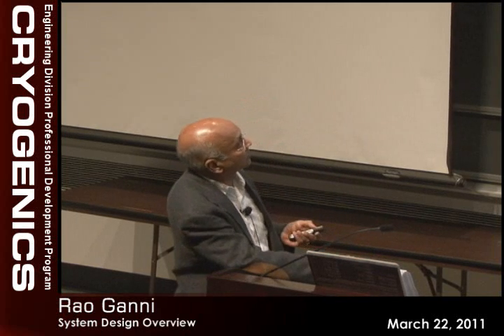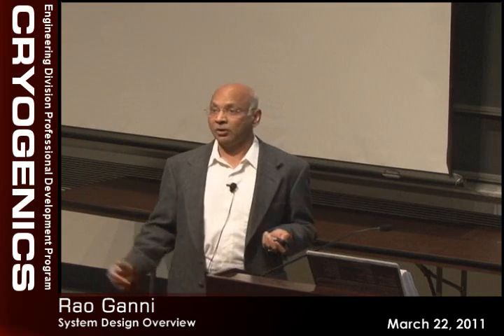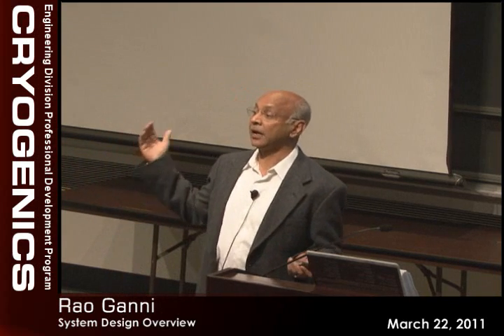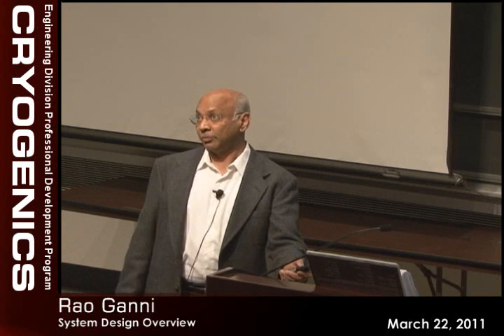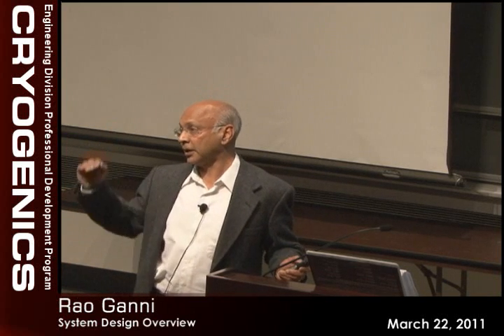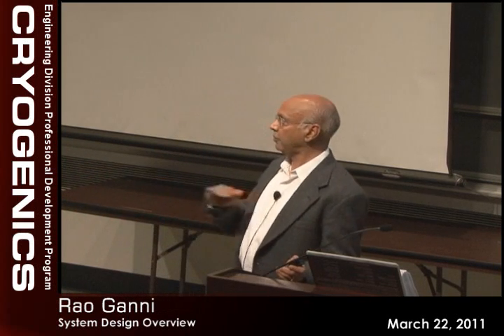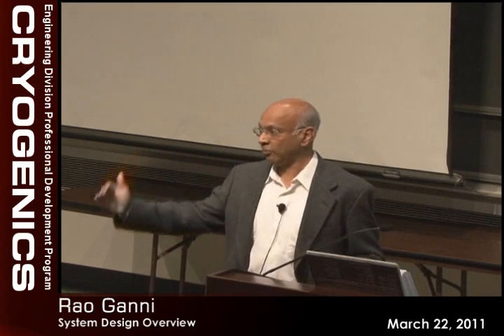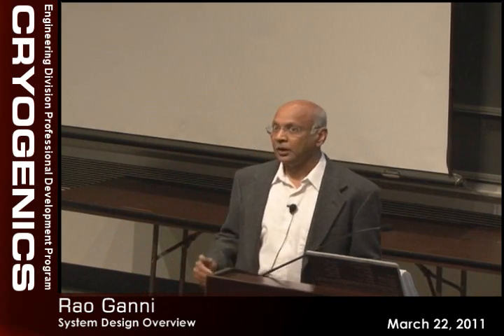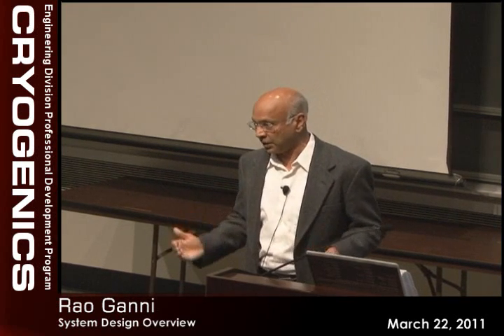You have to have different plans. And some of them are going to fail. You will have a turbine failure, or you will have a valve leak or something. And you can't take the whole experiment down because it's going to cost a lot more. You have to allocate for some critical failures and be able to meet a certain minimum operation, and all has to be addressed. For every critical component, we normally try to look at what happens if this fails, and where are we going to operate before we have a maintenance we can do. So we try to look at this from many angles now because of the experience we got as users, and that's what we want to bring up.